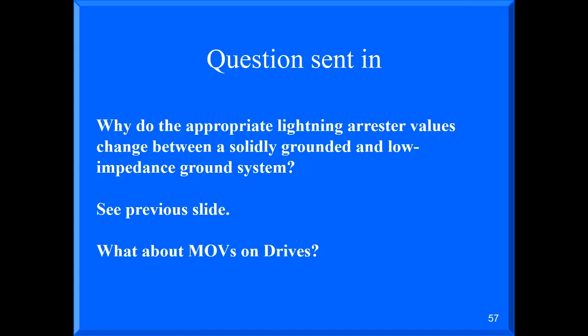If I go into a pulp and paper mill, 95% of them have high resistance grounded systems at 480 volts. Michael, are you data centers? Do you have HRGs in all the switchgear? No. We only have the resistance grounding up on the medium voltage side on the utility transformer. Because of the generators. And you need to protect the generator. That's surprising to me. I've never seen a data center. Well, they will definitely have low resistance. Generators, you talk to the generator. Yes, and they've got generators.